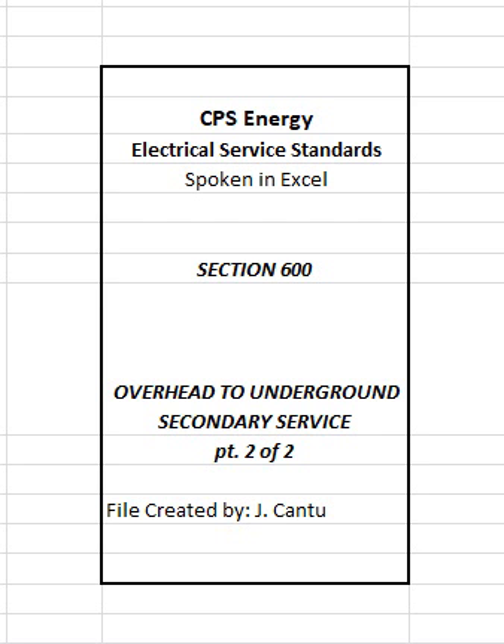Note 1. Where communication utilities are approved to share trench with CPS Energy, a second inspection may be required where flowable fill is interrupted to install such utilities. Note 2. CPS Energy shall not accept nor take ownership of conduits until after service lateral has been installed.